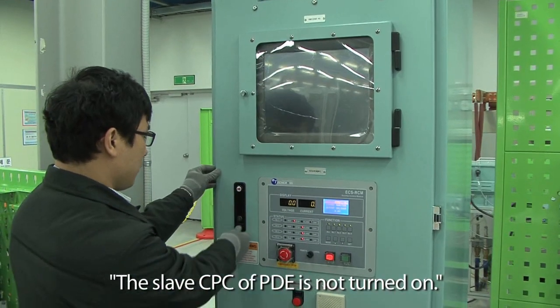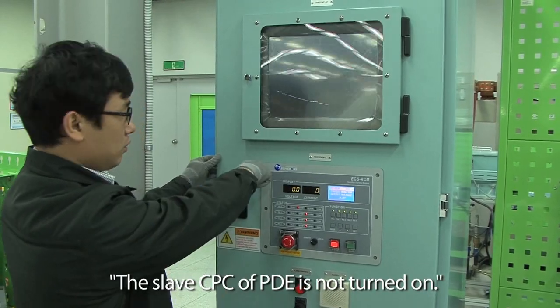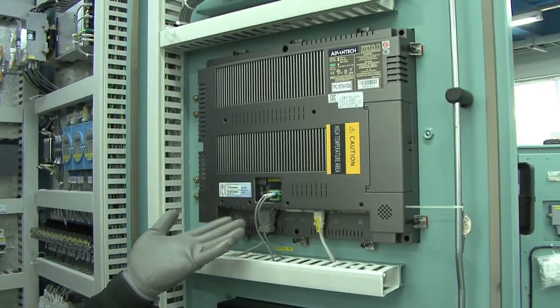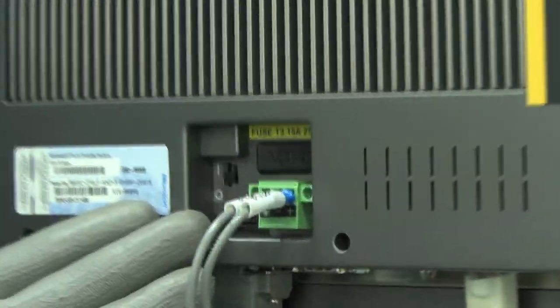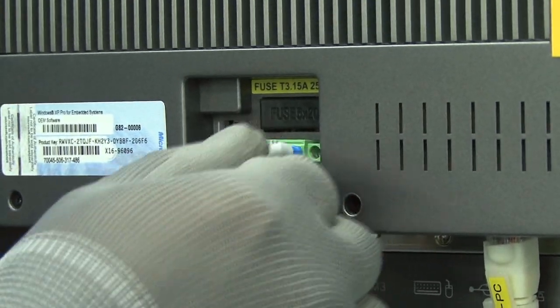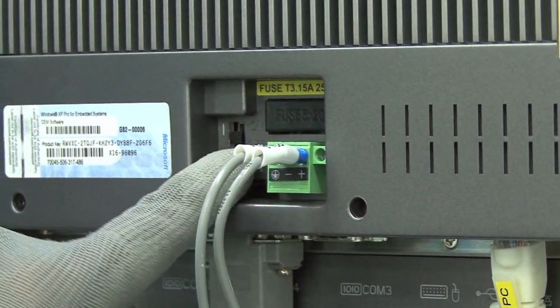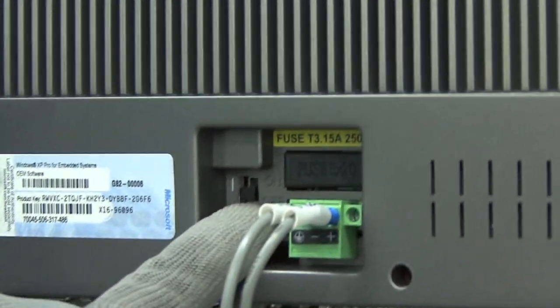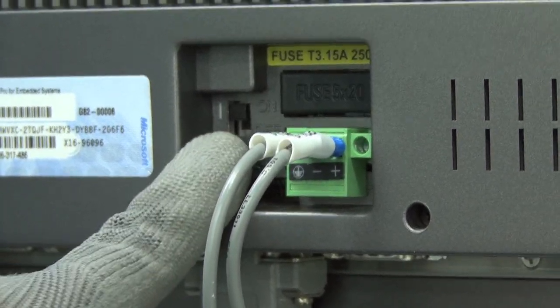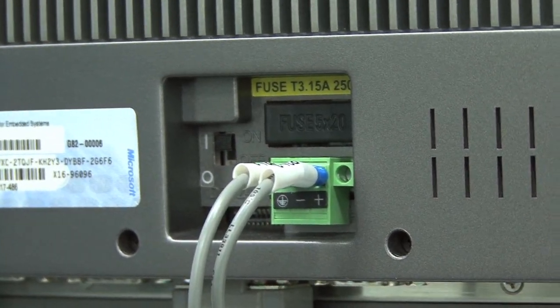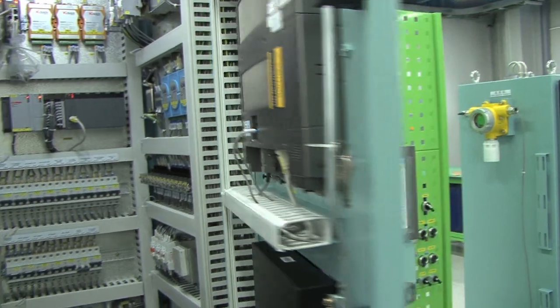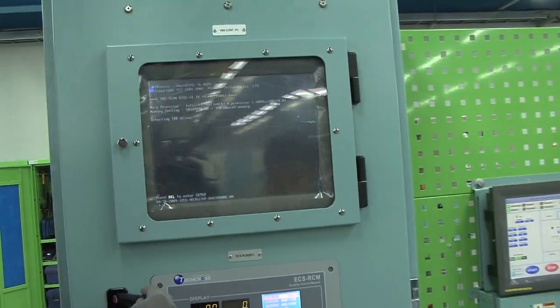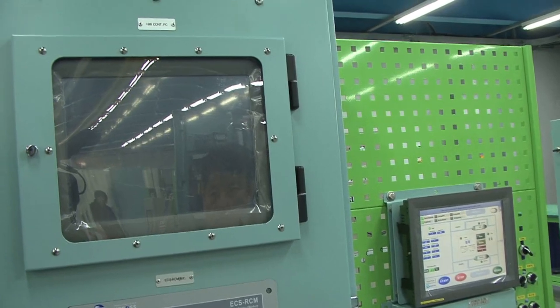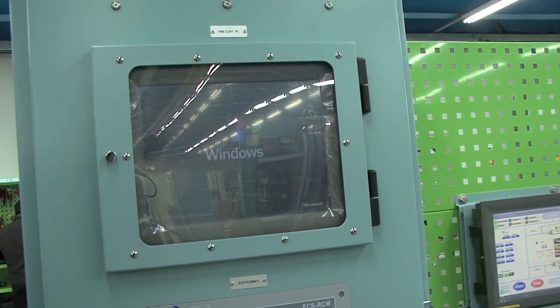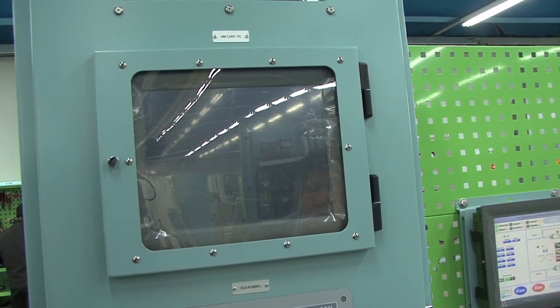Problem. The slave CPC of PDE is not turned on. Solution. Check the power of slave CPC of PDE, as shown in the picture. Check if power and communication cables are connected properly. Check if the power switch is on. If it is not turned on with its switch on, check the fuse of CPC. If the fuse is broken, replace it with new fuse for CPC in the spare parts. Refer to maintenance of spare part for replacement. If the same problem persists, please contact the manufacturer.